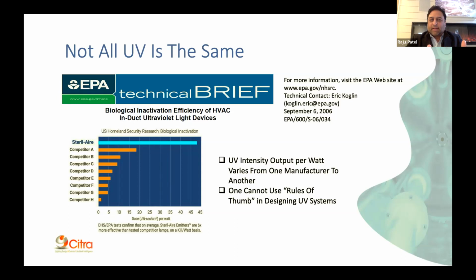When we were vetting UV manufacturers, we asked how do we tell the difference. Fortunately, there was a study from the EPA and the Department of Homeland Security, since Homeland Security is interested in UV from a bioterrorism perspective, and all GSA buildings are required to have UV. This study bought a handful of different brands and tested them, documenting output and dosage performance. You can see Steril-Aire, at operating temperatures within an air handler, had six times the output of its nearest competitor. So we look for actual testing and the science behind this.